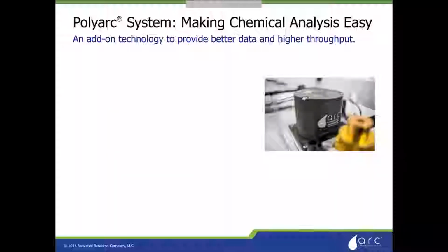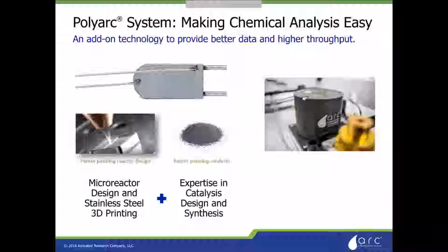So the PolyArc system is a catalytic reactor, as I mentioned, that goes after your GC column, but before your FID. And this device is built using 3D printing of stainless steel. So that's direct metal laser sintering of stainless steel. And we do that because we want to get very controlled geometries inside of this reactor so that we can do 100% reactions to methane of any analyte without affecting your chromatography.